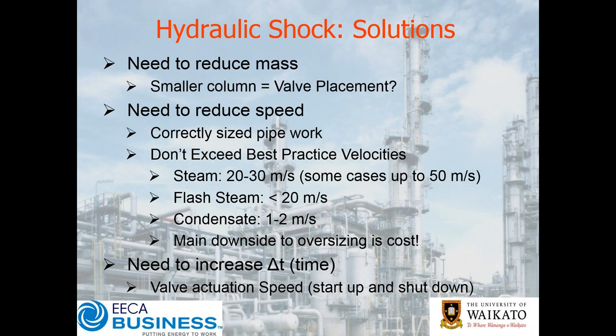Depending on the nature of your process and the system you're working with, you'll have different tolerances in terms of performance versus maintenance requirements. If you're demanding continuous operation and don't want to tolerate a failure, that needs to come through at the design and specification phase and be reflected in your maintenance and condition monitoring of those assets. It's very important to get your sizing correct. You may not need to oversize if you get the specification right and have the ability to do a hot change-out of a trap — which is quite achievable with the correct installation.